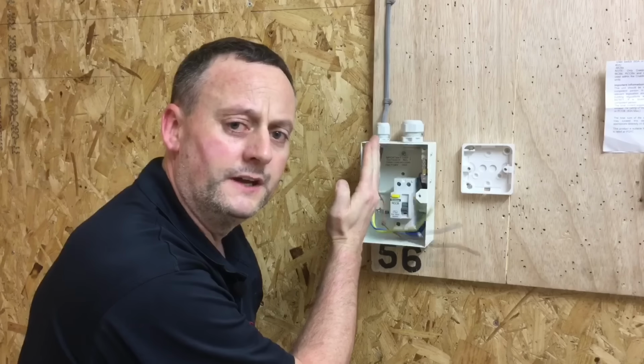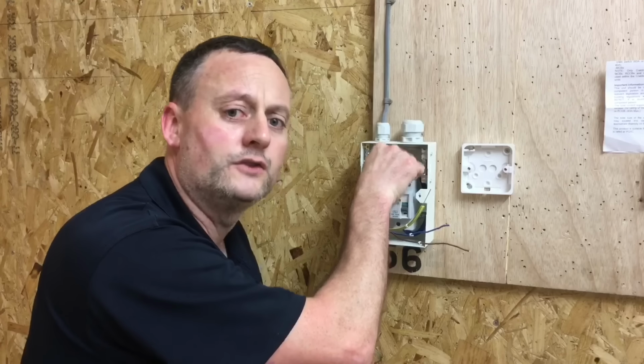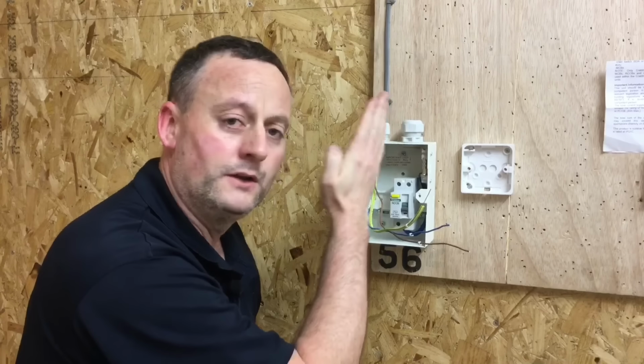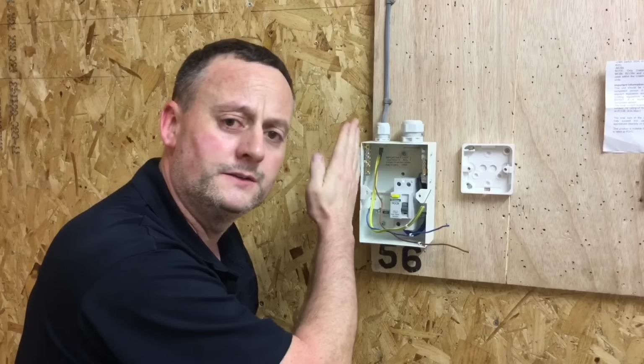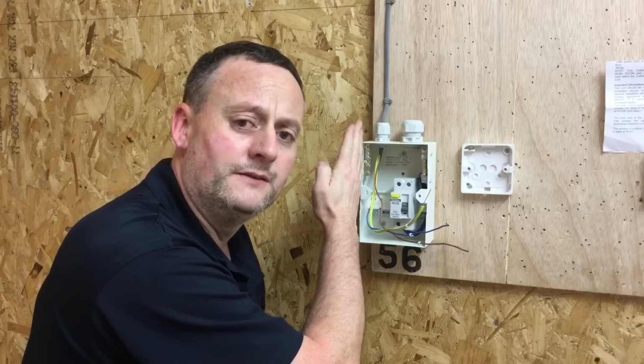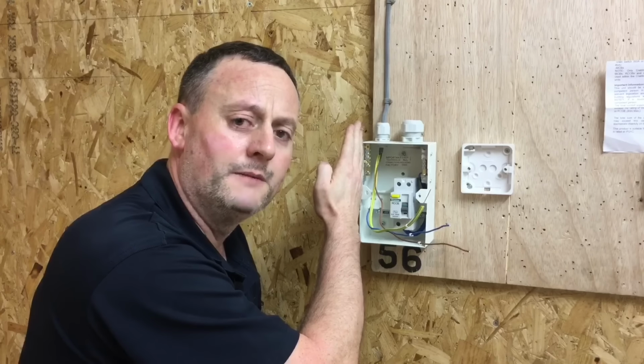The one next to that would be circuit number 2. We identify them in the event of us needing to remove the circuit. When I disconnect the line conductor out the top of the breaker with number 1 on, I'll be looking in the neutral bar for number 1 and the earth bar for the circuit protective conductor number 1, in order that they can be removed from the distribution board itself. So let's look how we're going to terminate the conductors and dress them neatly now within the consumer's unit.